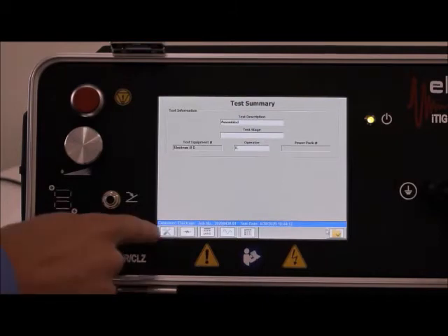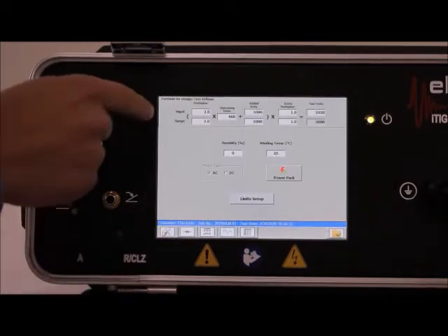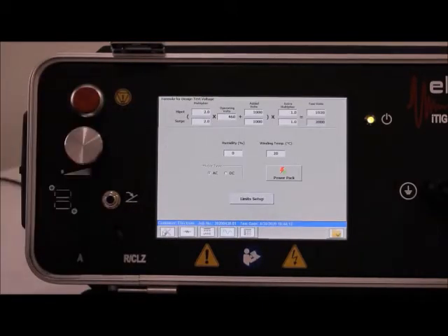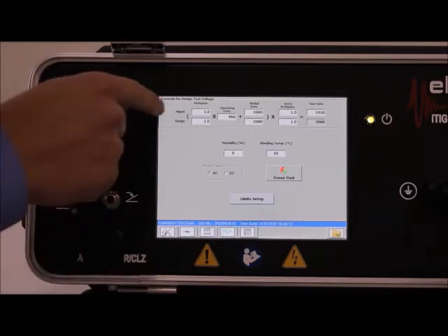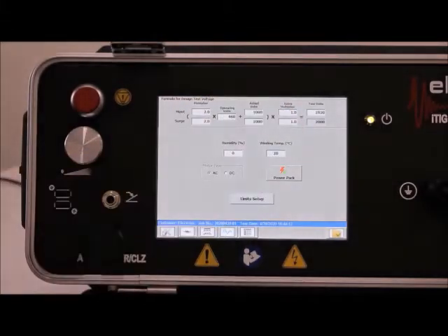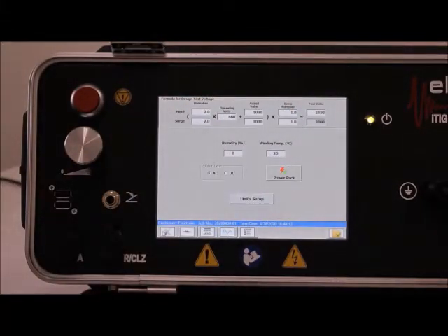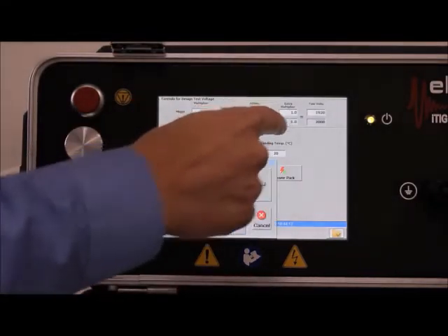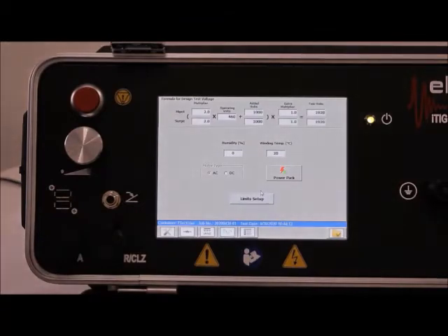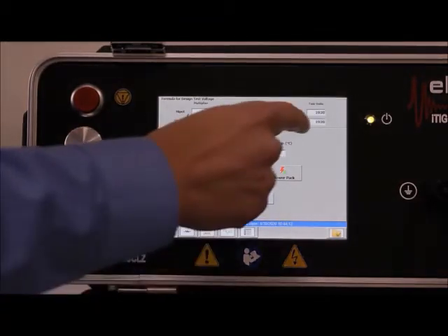Next step here is the setup screen. At the top we have our hipot and surge test voltage formulas. The instrument defaults to 2 times the operating voltage plus 1000. You can see here that I've already changed the recommended test voltage for the surge test to 2000. If you'd like to change it back to the recommended voltage, you can just click any of the white fields, hit enter. Now you're back to our 1920. Or enter in whatever voltage you prefer.